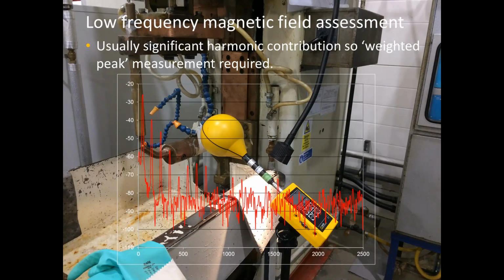And what a weighted peak probe does is it measures all of that. It assesses the whole thing. So this picture is a real world example of the harmonics generated by a 50 hertz resistance welder. And this meter, the ELT400, is looking at the whole spectrum. It's weighting it, and it's coming up with a percentage of one of the action levels, either the low action level, high action level, or limb action level.